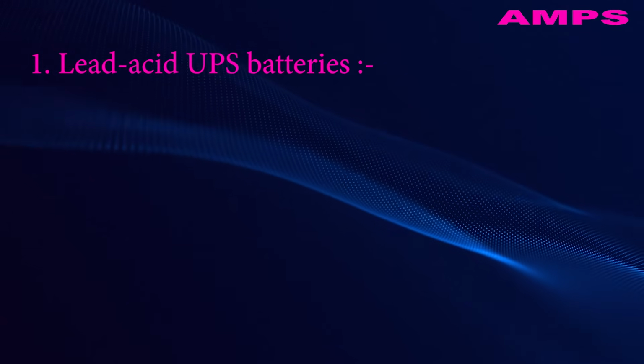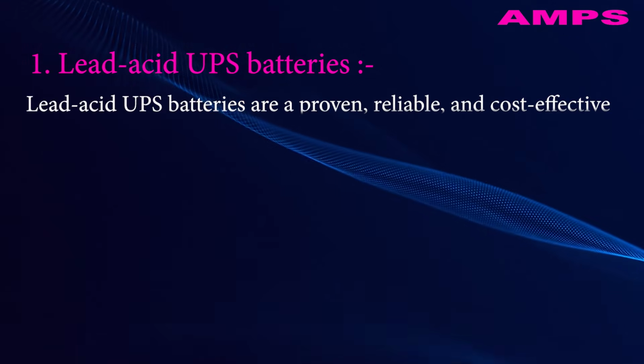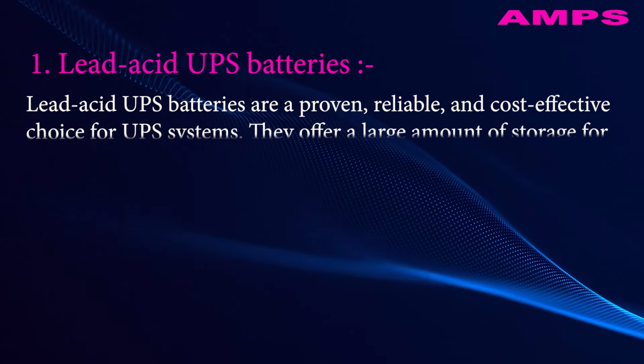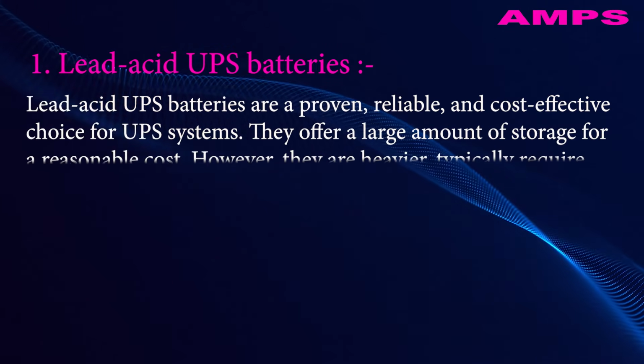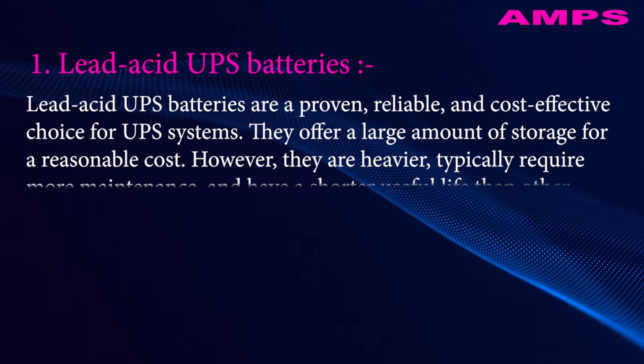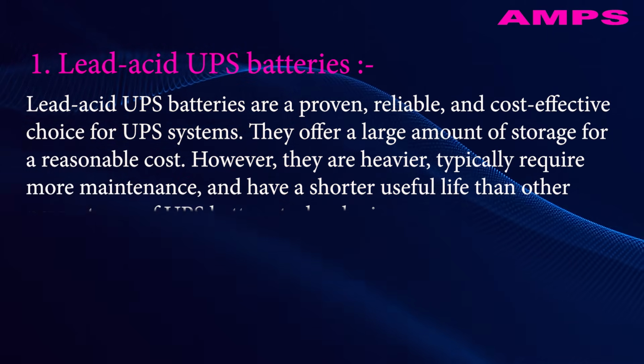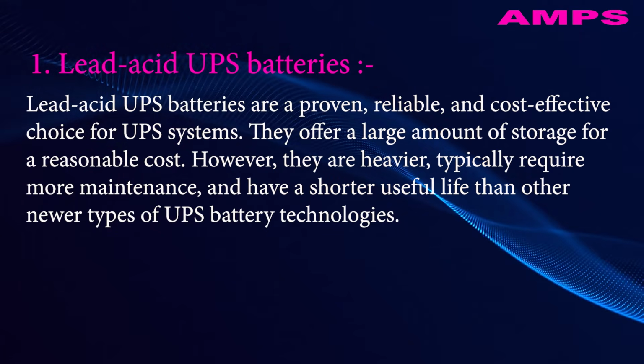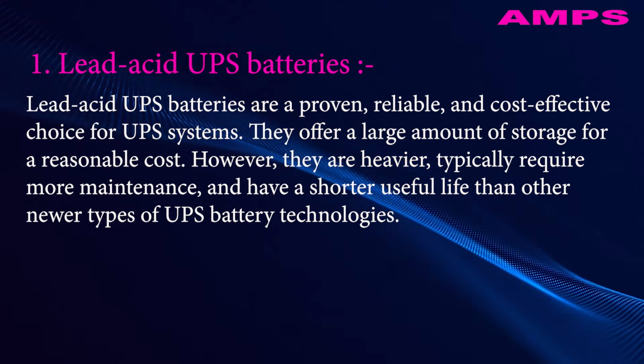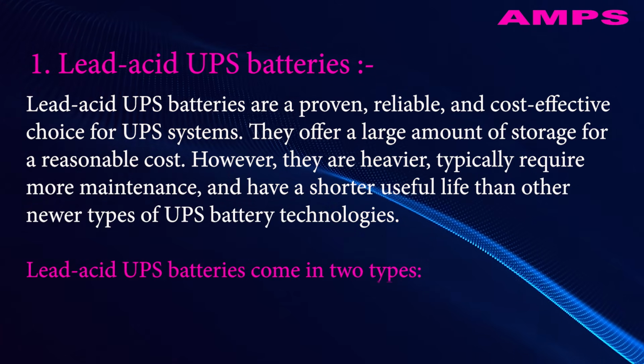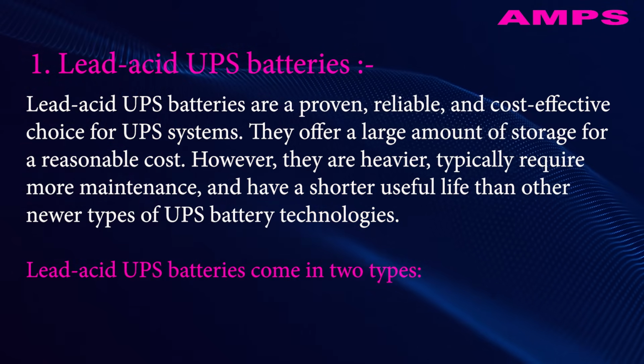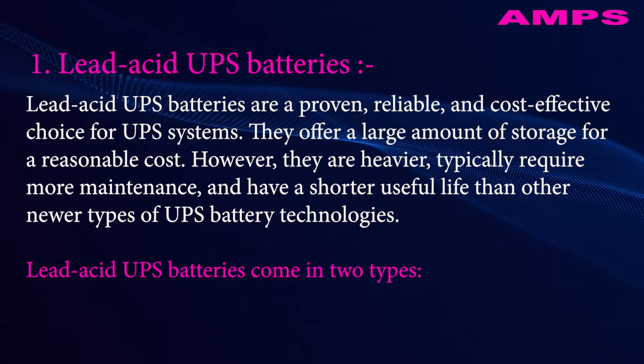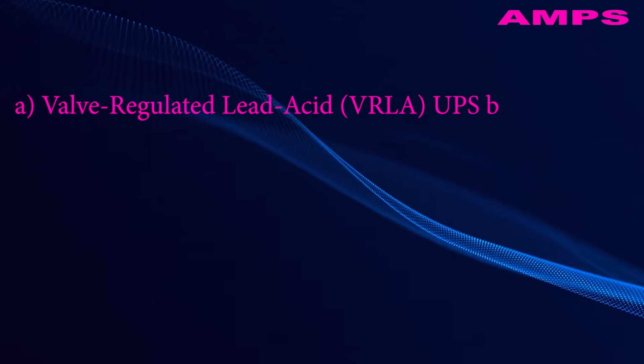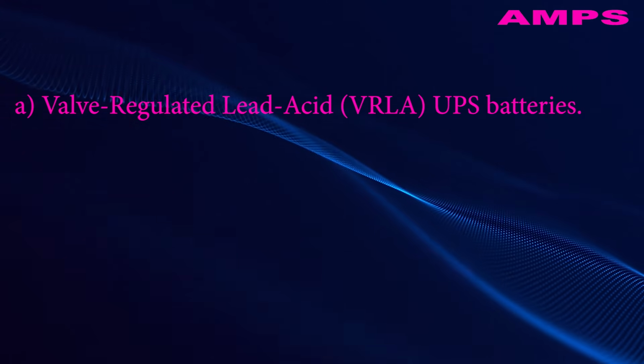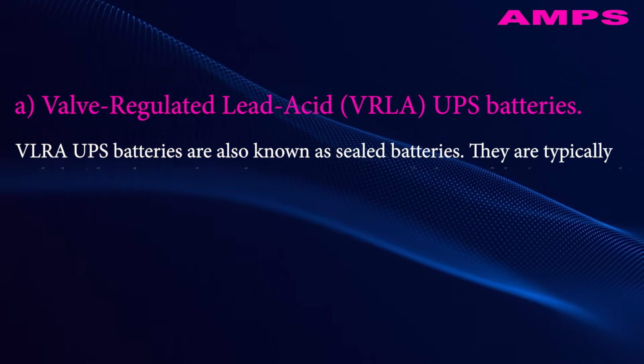Lead-acid UPS batteries are a proven, reliable, and cost-effective choice for UPS systems. They offer a large amount of storage for a reasonable cost. However, they are heavier, typically require more maintenance, and have a shorter useful life than other newer types of UPS battery technologies. Lead-acid UPS batteries come in two types. 1. Valve-regulated lead-acid, VRLA, UPS batteries.